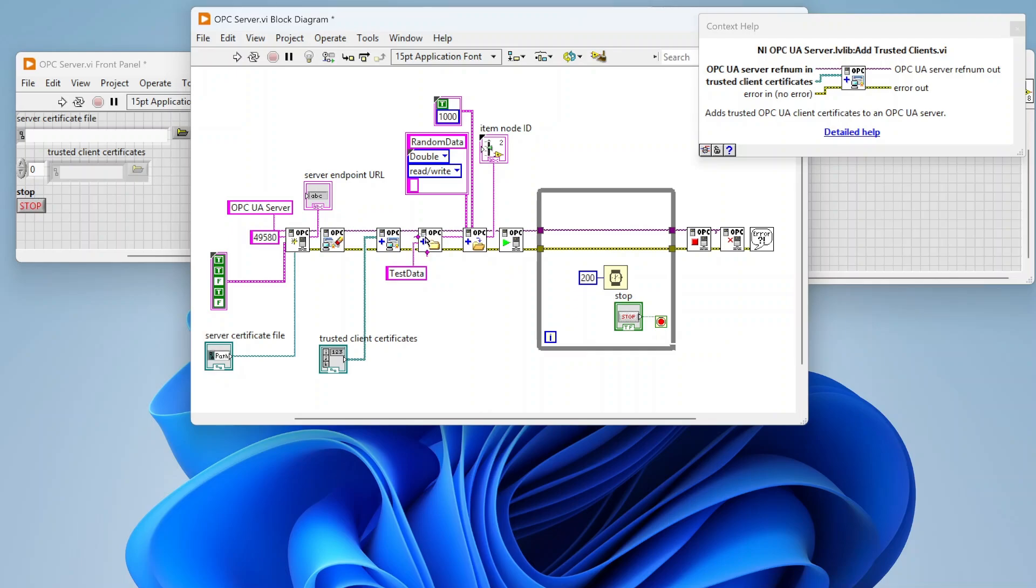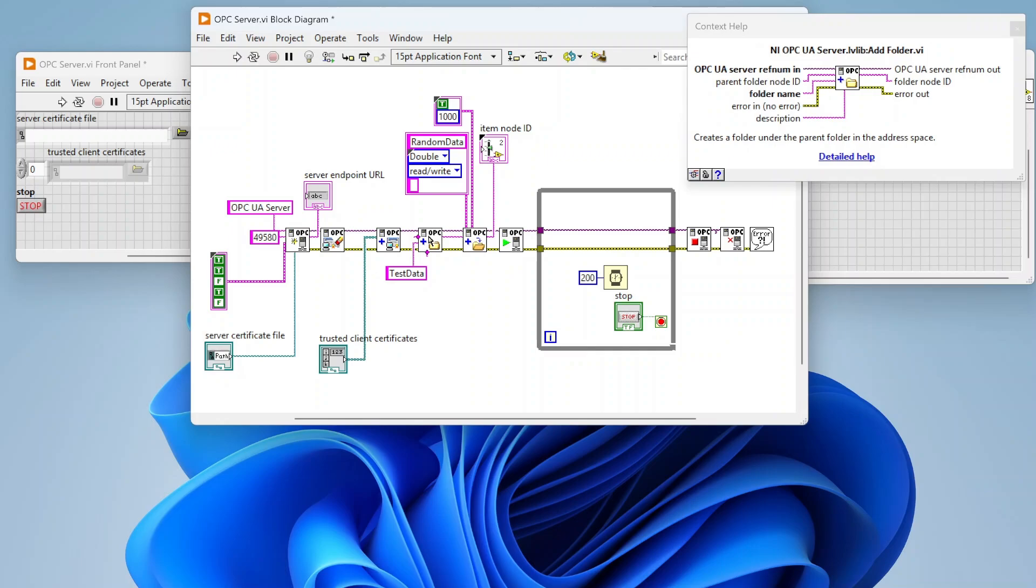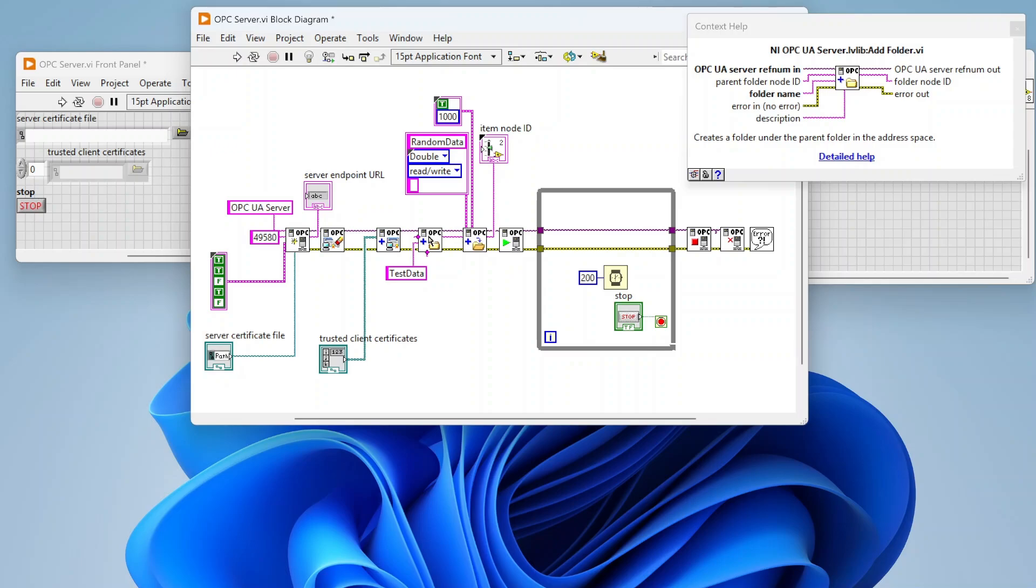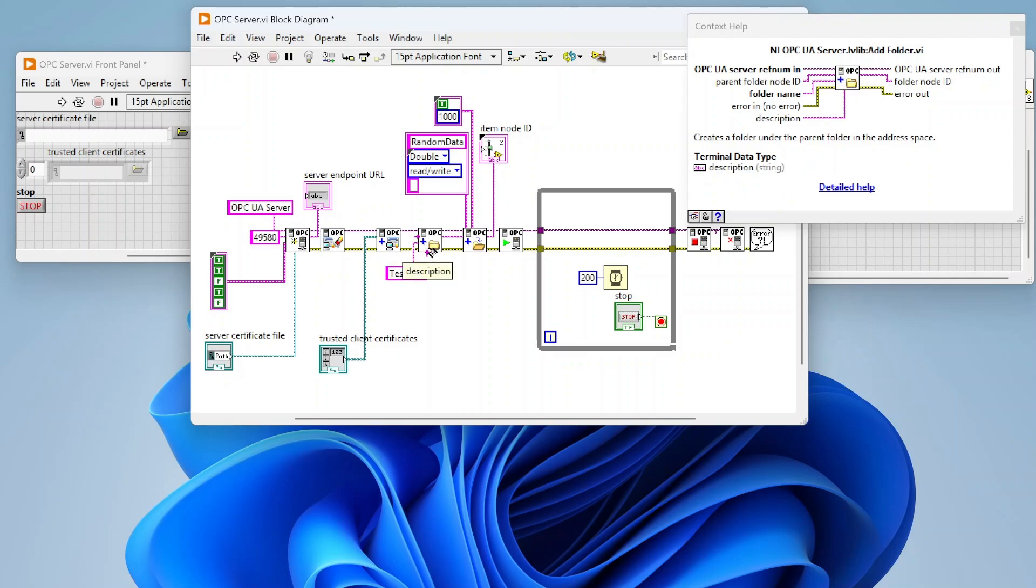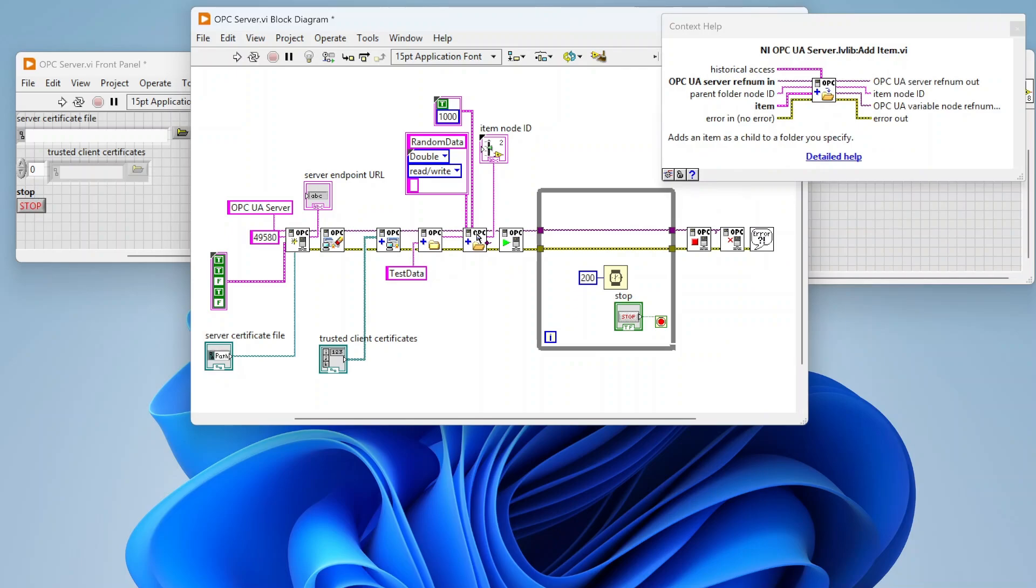There's this add folder function. One of the cool things about OPC is you can create a folder structure. You're going to have nodes, and in those nodes you can have folders, and those folders can have subfolders, levels deep, with data stored in those locations. On a single server I can create multiple folders so my data is well organized, and in those folders I can create subfolders that organize data differently. In this case we're creating a folder called test data. There's this parent folder node ID that I left unwired, meaning it's just going to put it under the main node.